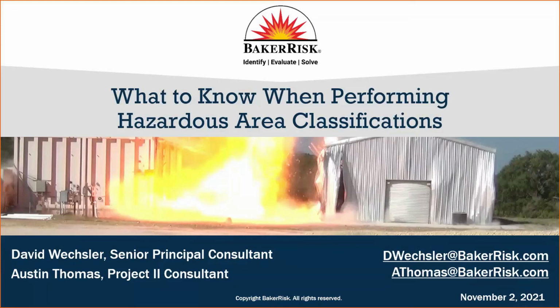Well, I would say there's not a discrepancy other than the fact they're looking at different objectives. If you recall, when we went through the earlier slides, we mentioned that the purpose of the hazardous area classification was to control ignition sources within defined source conditions. We are not looking at classifying the world, but rather we're looking at localized control and seeing what are the things we can control that are in immediate control.